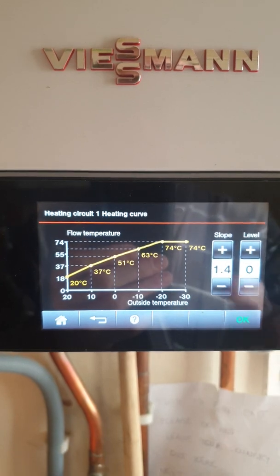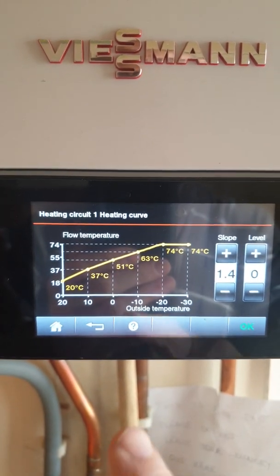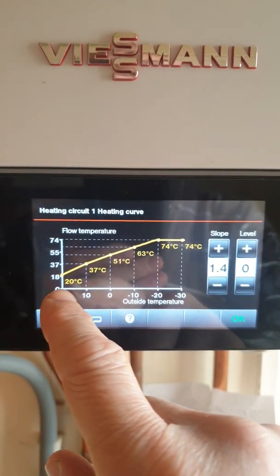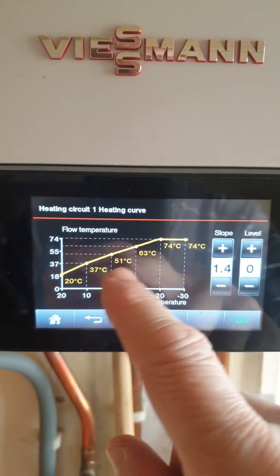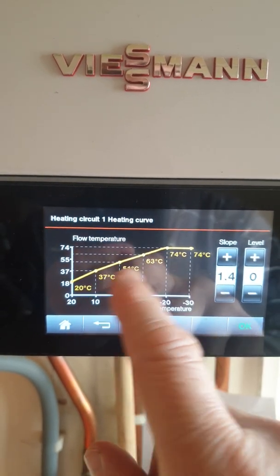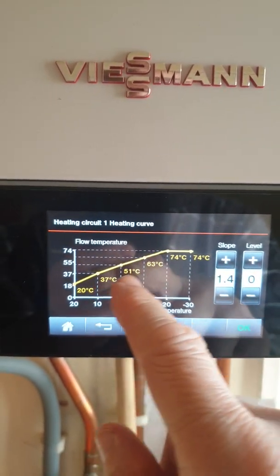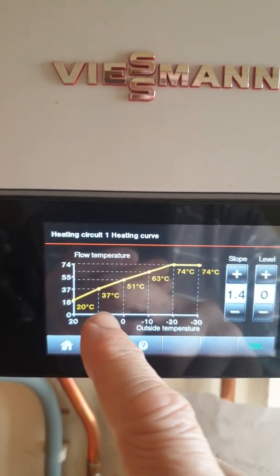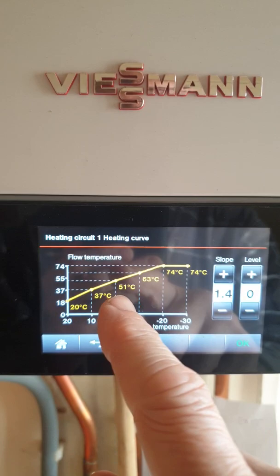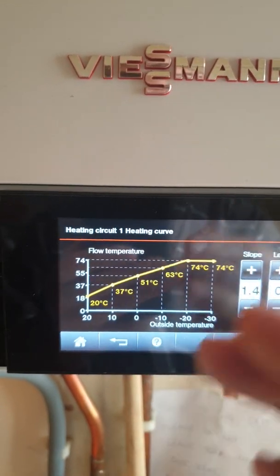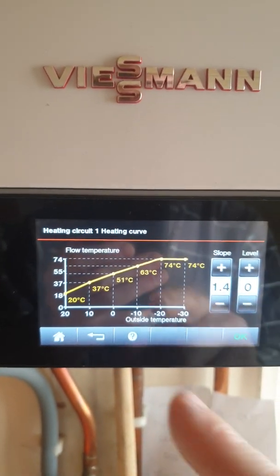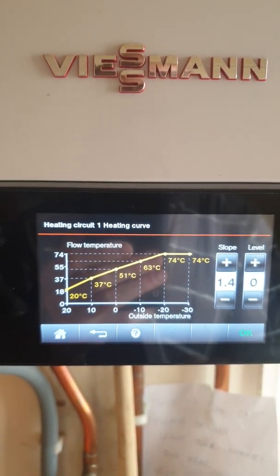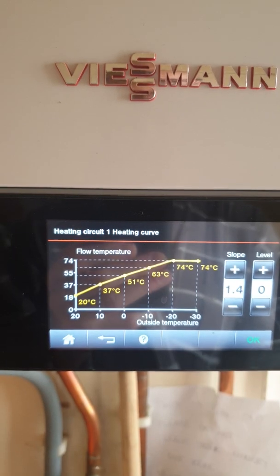Slope basically is going to adjust the curve to suit the type of system design you've got. It works on the principle of setting the mean water temperature, but the boiler doesn't know the mean water temperature — it knows the flow temperature. So this is extrapolated across into flow temperatures. We're setting this to give the correct flow temperature to achieve the correct mean water temperature to get the right heat output from the boiler, so that the radiator in the room matches the heat loss from the room to outside.